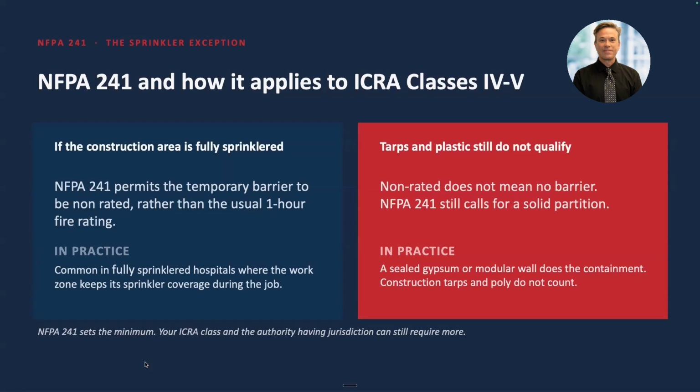Matter of fact, over the years, and one reason we asked our colleagues from STARC to talk about their barrier protection, is people were using inappropriate barrier protection. It's either not fire rated at all, it's combustible, it doesn't meet any requirements for protection. So the barrier has to be smoke tight, has to control dust, and also has to provide some level of protection for fire.